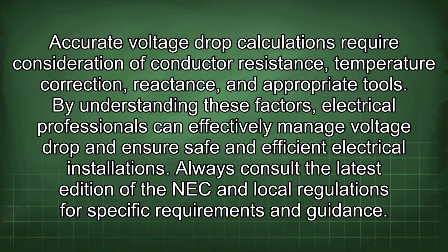Accurate voltage drop calculations require consideration of conductor resistance, temperature correction, reactance, and appropriate tools. By understanding these factors, electrical professionals can effectively manage voltage drop and ensure safe and efficient electrical installations. Always consult the latest edition of the NEC and local regulations for specific requirements and guidance.